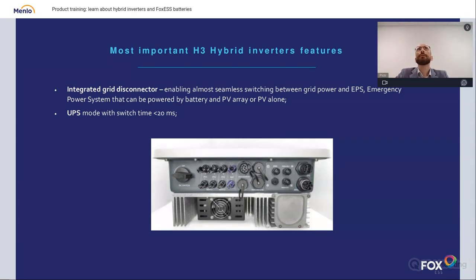The most important hybrid features are that they are really high powered. They can operate in a full off-grid mode. They have an integrated grid disconnector. So as you've seen this EPS box as an external device, H3 and H1 come with this EPS box built into the unit. So you don't have to use an external EPS unit to power the client.